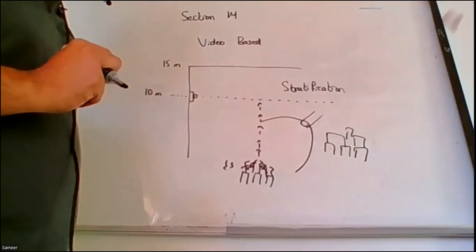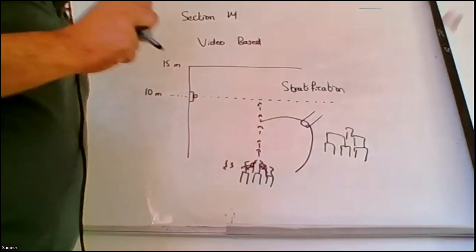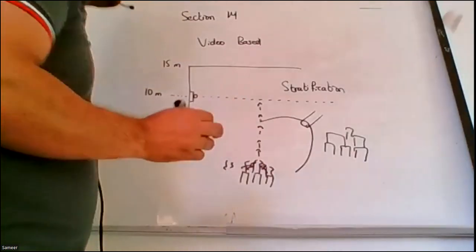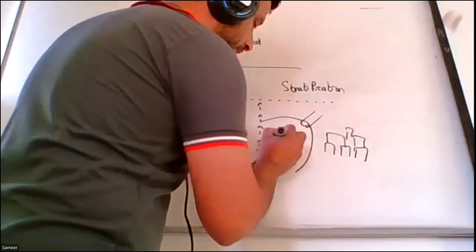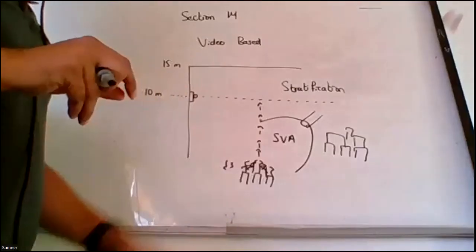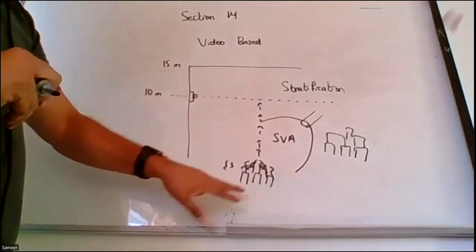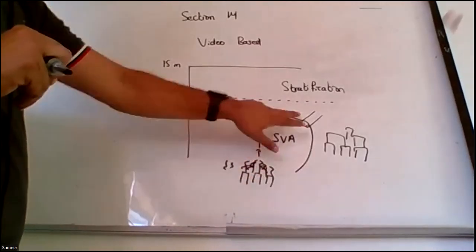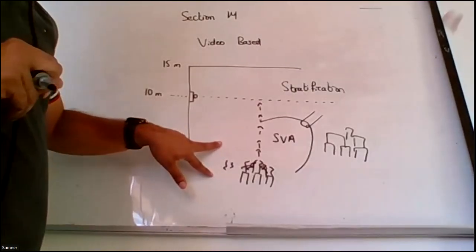Now, these cameras or video-based detectors are installed the same way as we do CCTV. We do the surveillance vulnerability analysis, SVA. We perform the SVA and identify which conical vision should be under the direct access of our cameras. Anyways, these are our materials. Now the video-based detector is installed. What will the video-based detector do? As soon as a smoke structure appears on top of the material, it will start taking photos and deliver them to the computer.